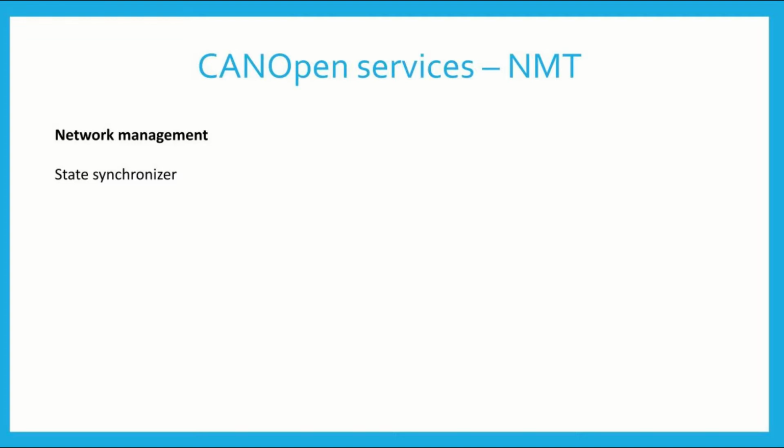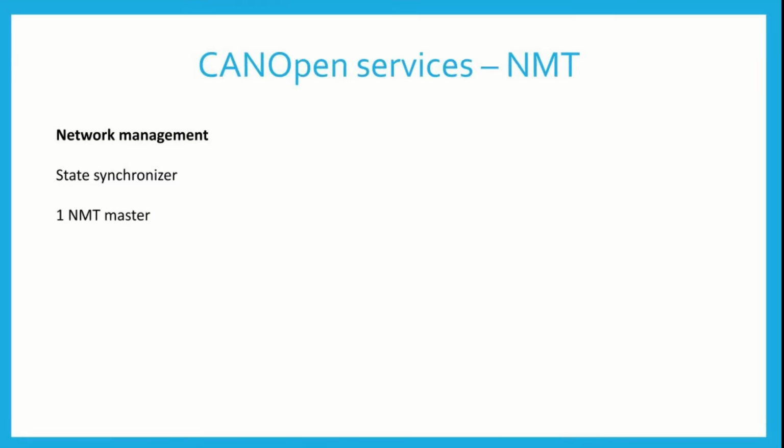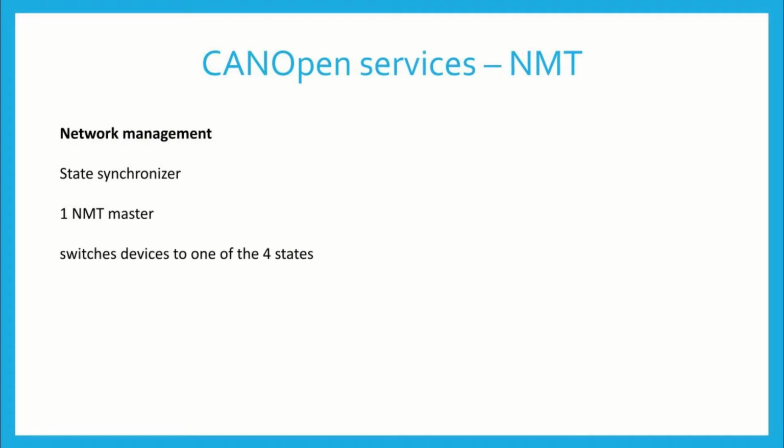The Network Management service takes care of synchronization of the state of each device on the bus. This message has a higher priority on the bus. There is only one NMT master on the bus and it ensures bus recovery. According to NMT states, the devices could be in one of four states.